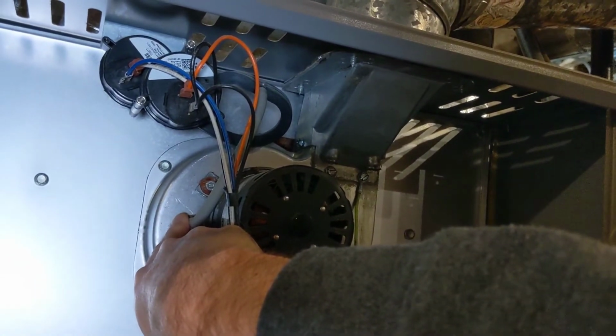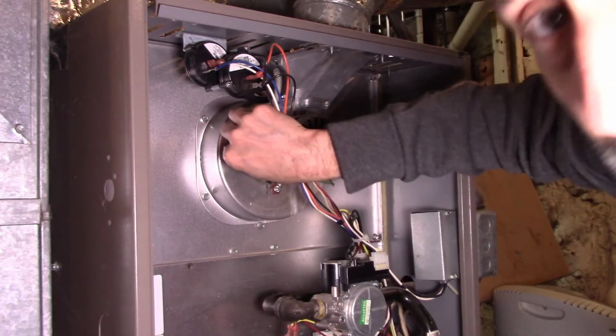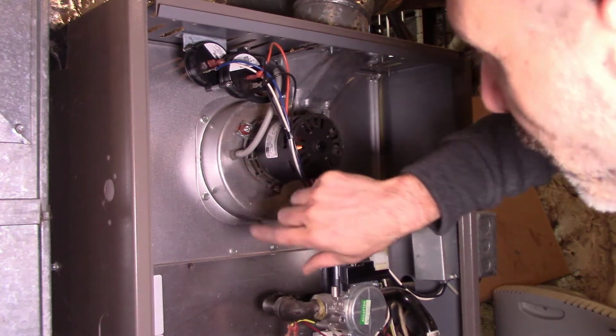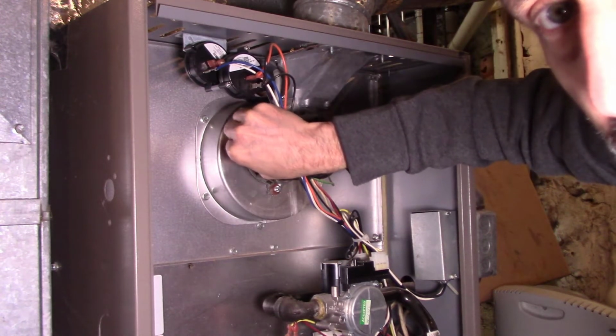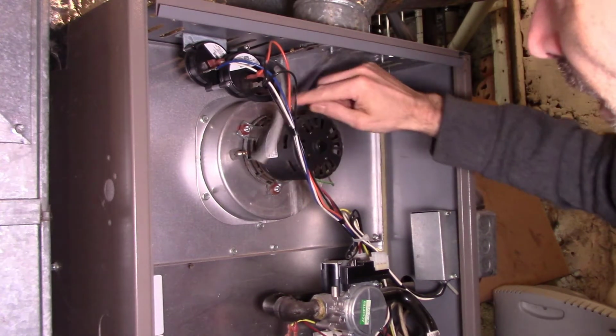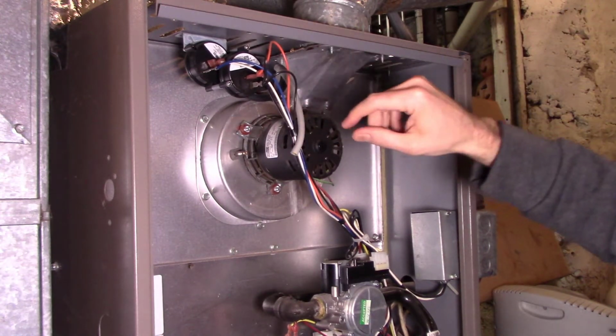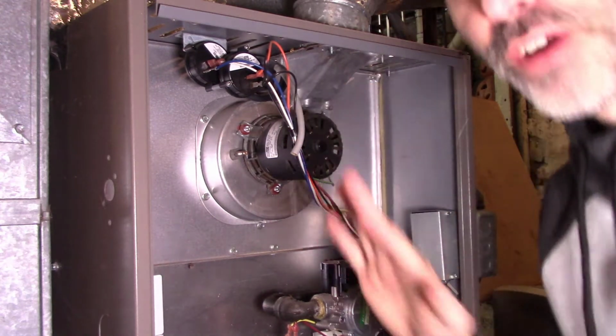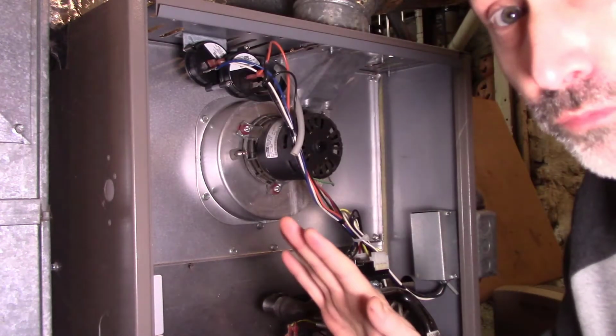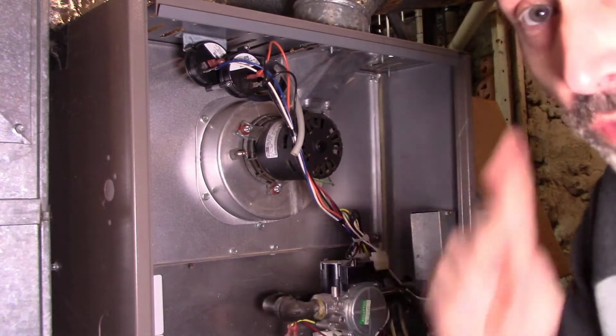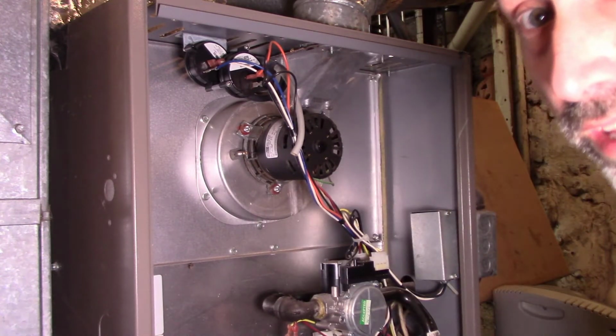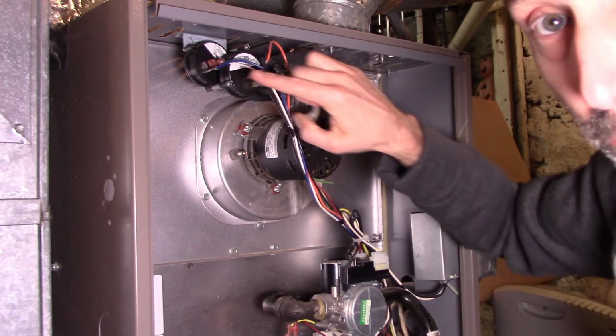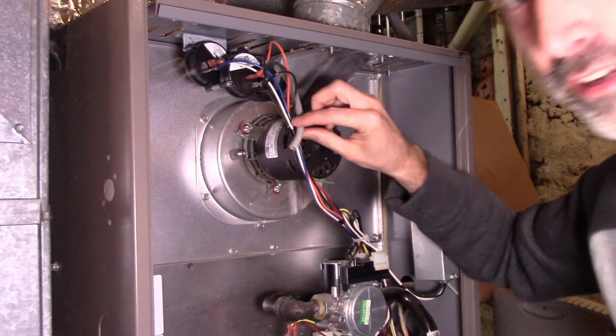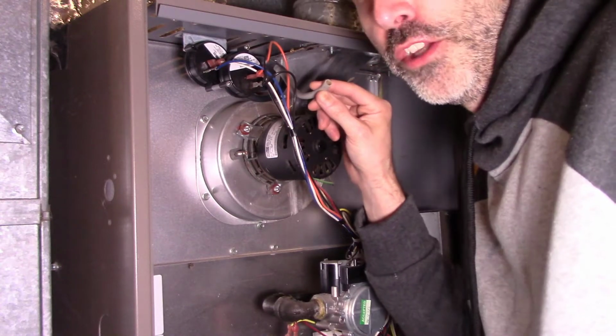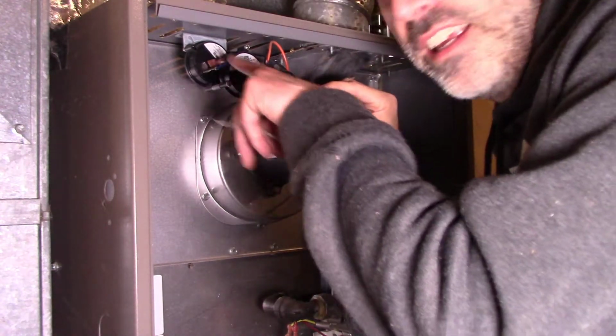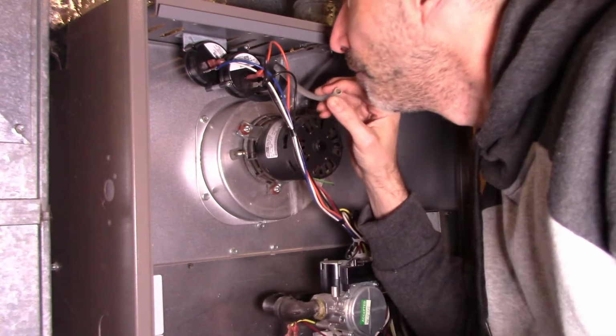Let me show you how to test that. The way I'm going to troubleshoot this, I'm going to pull the soft rubber tubing off of this little port here. Just be real gentle. It should come off. And then what I'm going to do is, I'm trying to do this for homeowners that don't have special tools. So the really low-tech way of seeing if it's your pressure switch is, and you may not like this, but I'm going to just suck on the tube with my mouth and listen to hear if I hear the switches click.